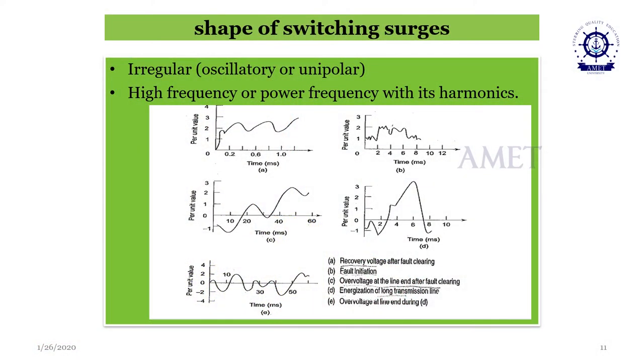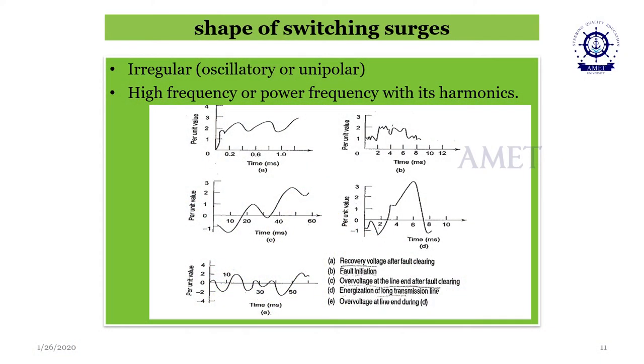So you can see here some five types of switching surges, because of the different activities performed by people, say the operations of the devices. One is the fault clearing. Due to fault clearing, A represents the fault clearing time. You can see the per unit value. The over voltage is defined in per unit against time, and the time is in milliseconds.